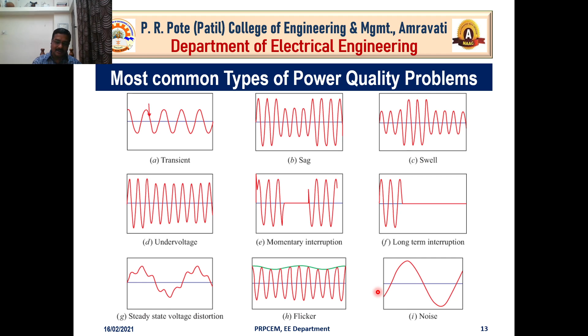Now let's discuss all these power quality events one by one. Voltage sags first. As far as the description of voltage sag is concerned, there is a decrease of the nominal voltage, the normal voltage level, between 10% to 90% of the nominal RMS voltage at the frequency, and that is for a duration of 0.5 cycle to 1 minute.